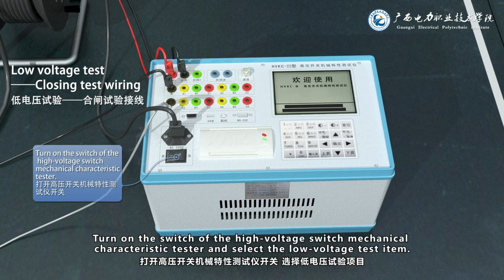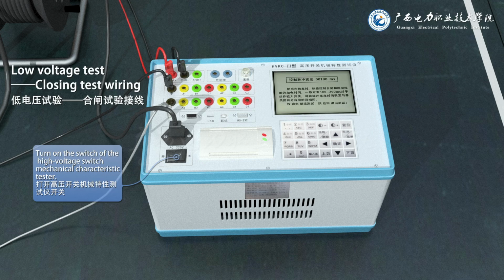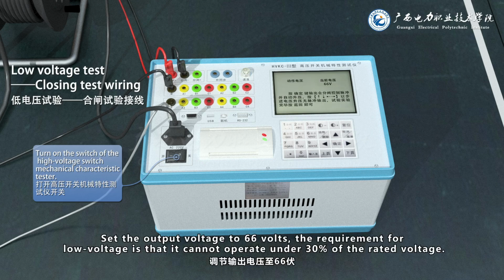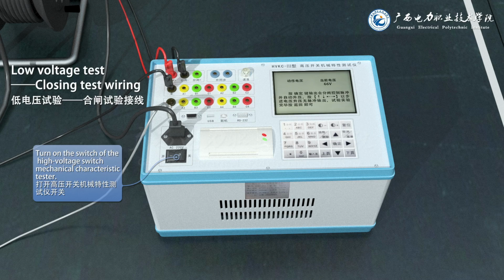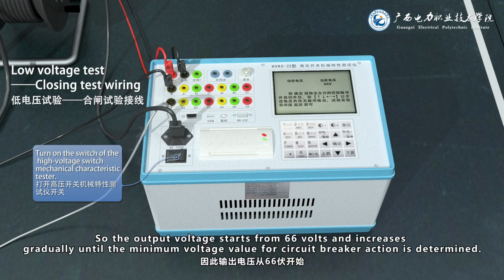Turn on the switch of the high voltage switch mechanical characteristic tester and select the low voltage test item. Set the output voltage to 66 volts. The requirement for low voltage is that it cannot operate under 30% of the rated voltage. So the output voltage starts from 66 volts and increases gradually until the minimum voltage value for circuit breaker action is determined.